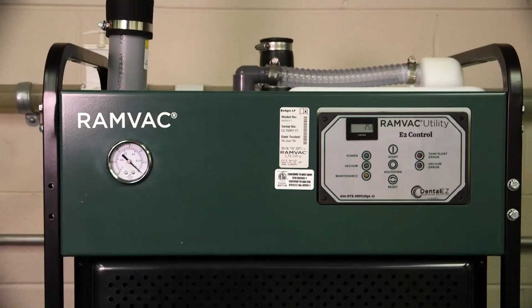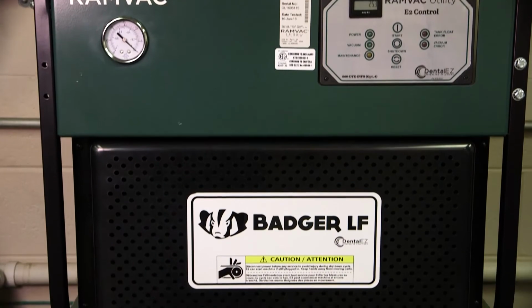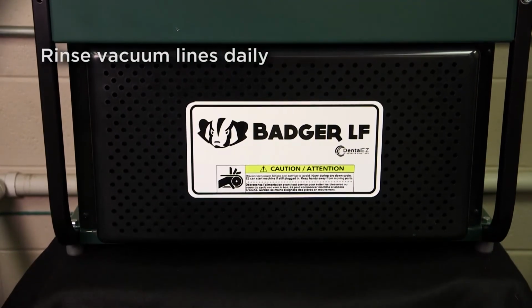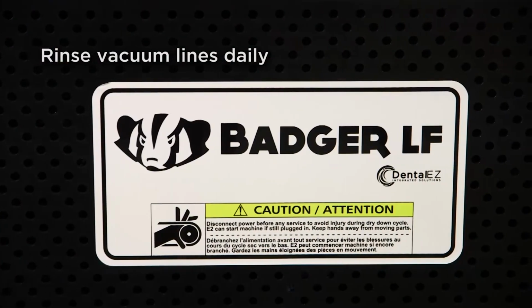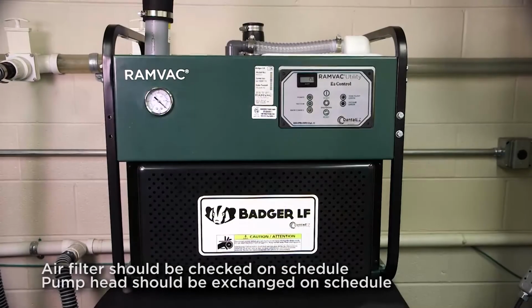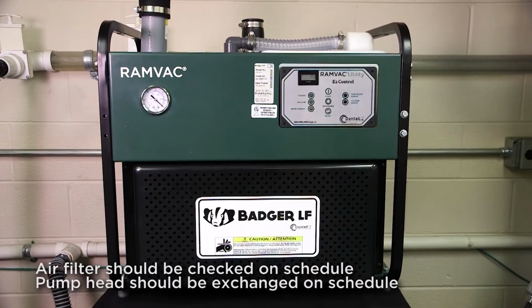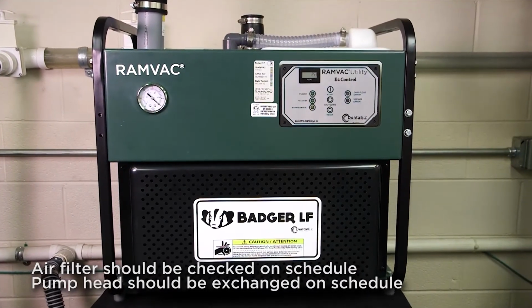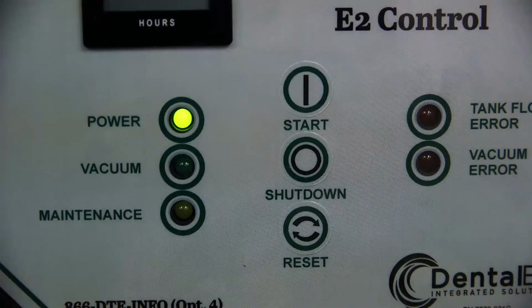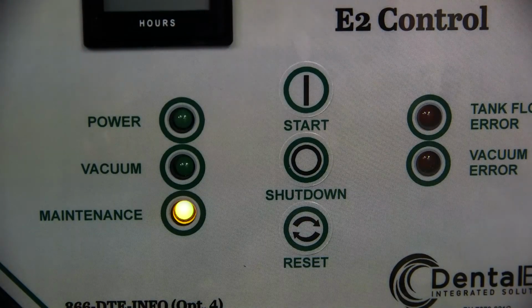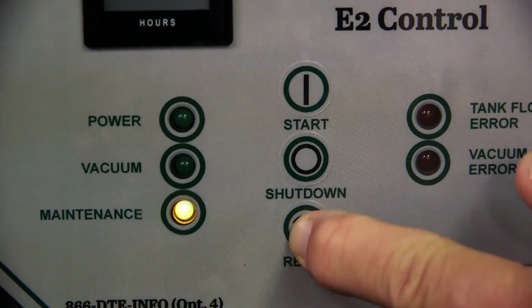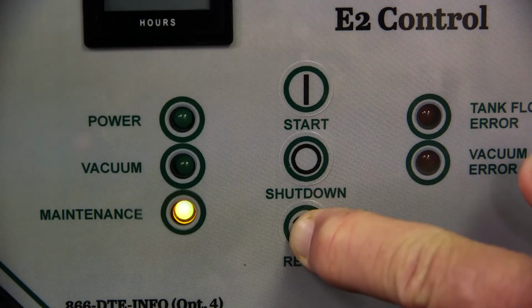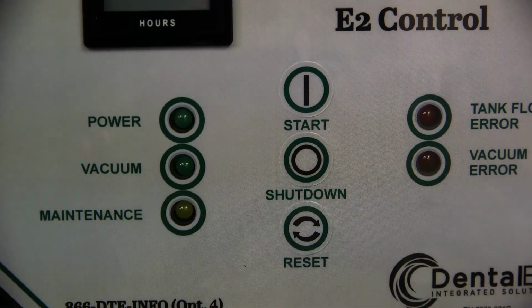The key points for trouble-free operation of the Badger LF include rinsing vacuum lines daily with the recommended quantity of liquid and line cleaner. In addition, the air filter should be checked on schedule and the pump head should be exchanged on schedule. The maintenance LED on the E2 control will illuminate every 1,000 hours. To reset the maintenance LED after maintenance has been performed, press and hold the reset button for 10 seconds until the maintenance LED begins blinking.